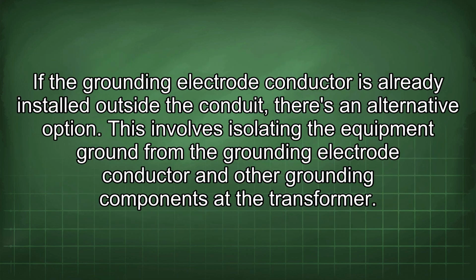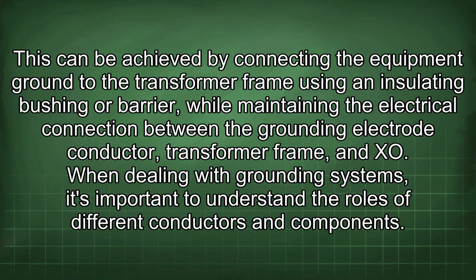If the grounding electrode conductor is already installed outside the conduit, there's an alternative option. This involves isolating the equipment ground from the grounding electrode conductor and other grounding components at the transformer. This can be achieved by connecting the equipment ground to the transformer frame using an insulating bushing or barrier, while maintaining the electrical connection between the grounding electrode conductor, transformer frame, and X0.